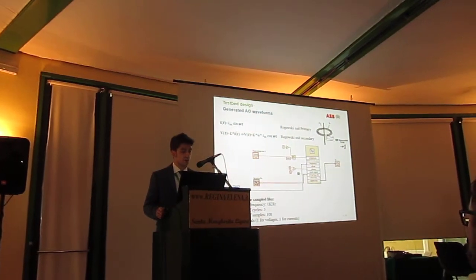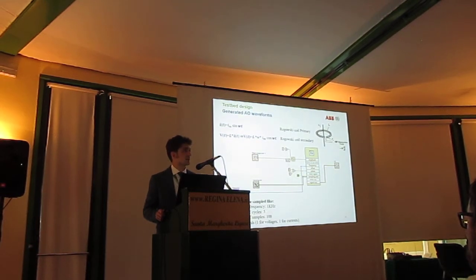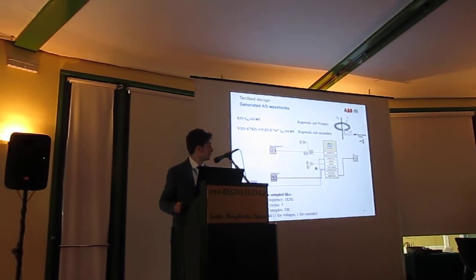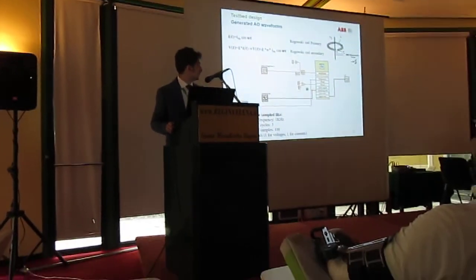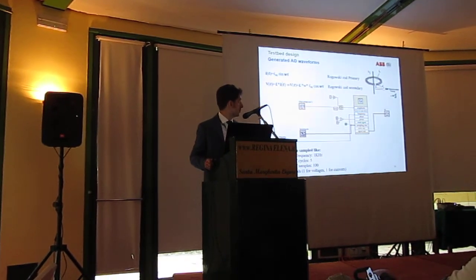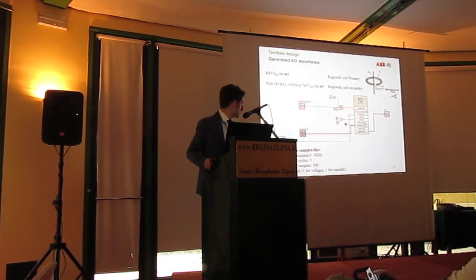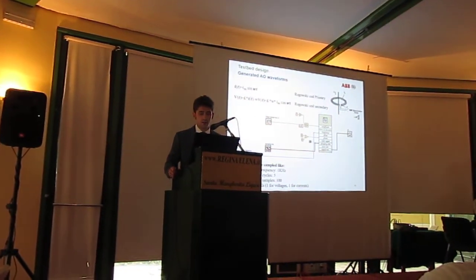Here you can also see some functions and coefficients which have been applied in our software based on exactly real conditions. For example, for the currents which are passing through the Rogowski coil, we have applied differentiation, because the measured signals have the intrinsic of a derivative of the current, and the other issues are with the sampling frequency of 1 kilohertz, 5 cycles of sampling, 100 samples per cycle. And as I said, only 2 analog outputs were required.